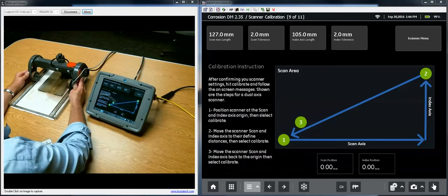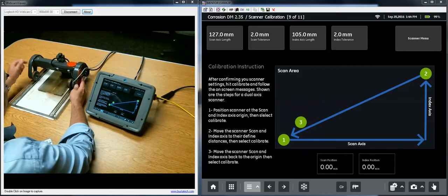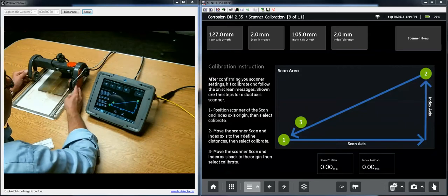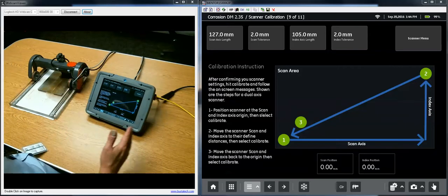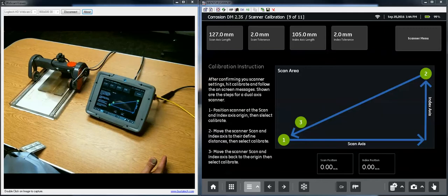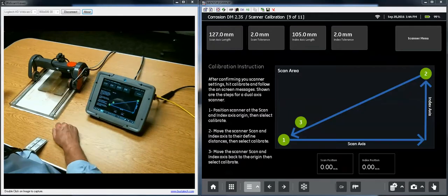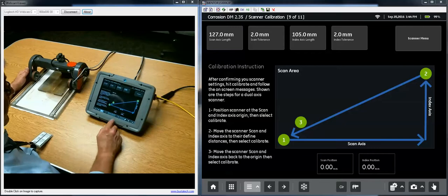And we have notches or lines scribed on our demo block, 5 inches or 127 millimeters apart. Again, if you were going to calibrate the scanner on, say, a measured 1 meter of your desktop, we'd set this parameter to be 1 meter. We're going to leave it set to 127 millimeters.